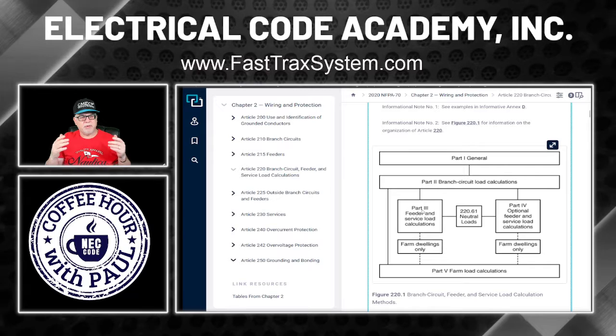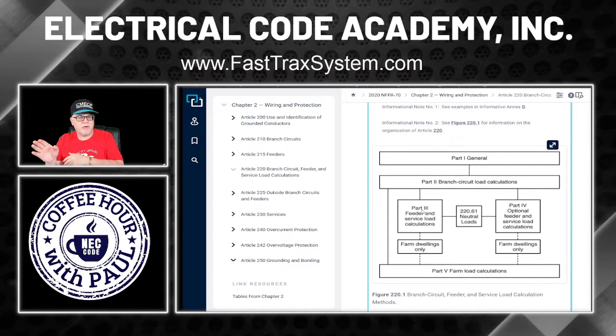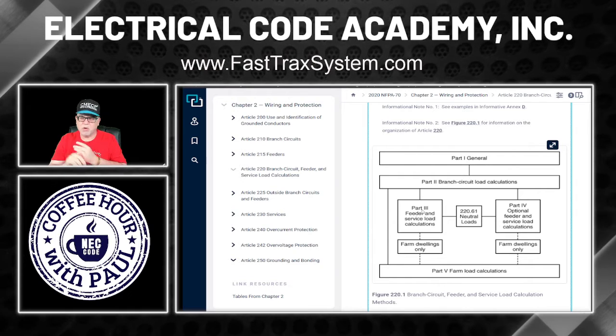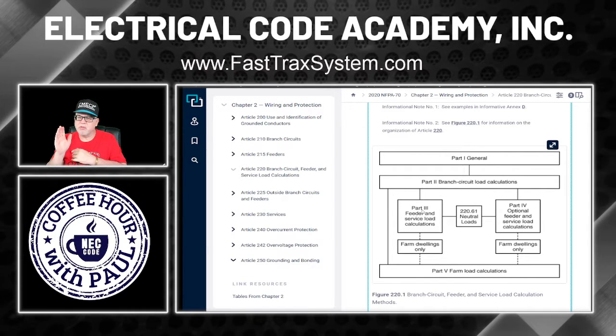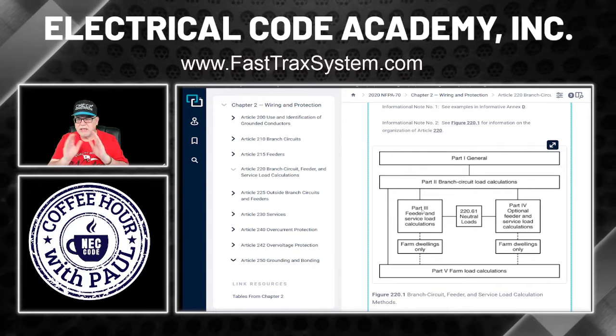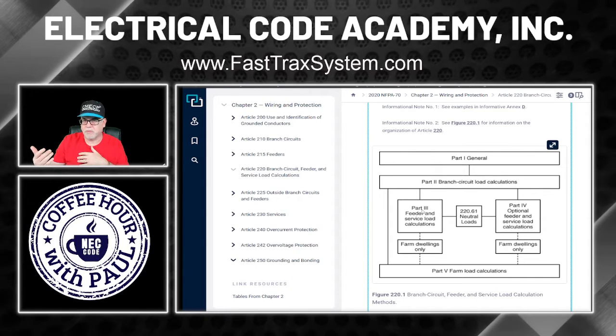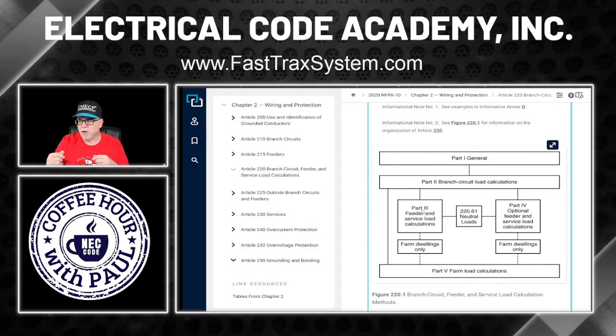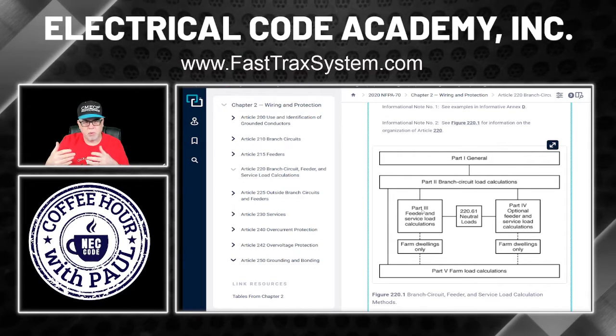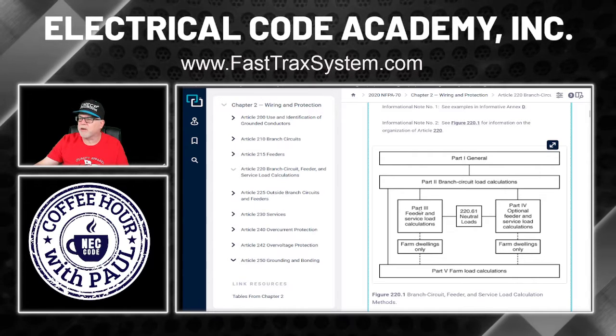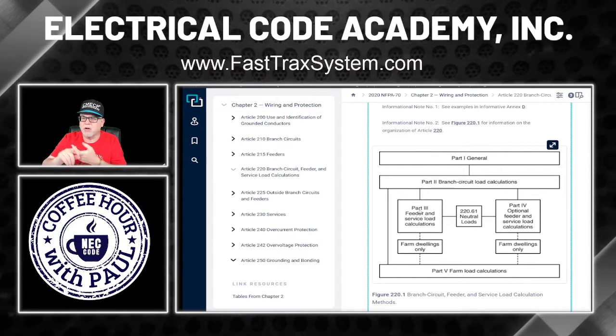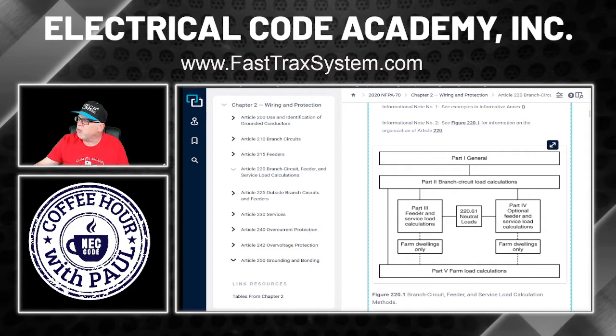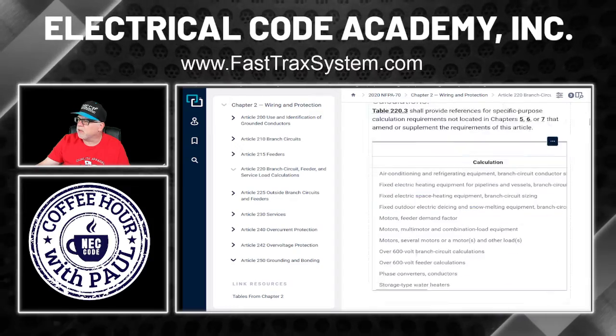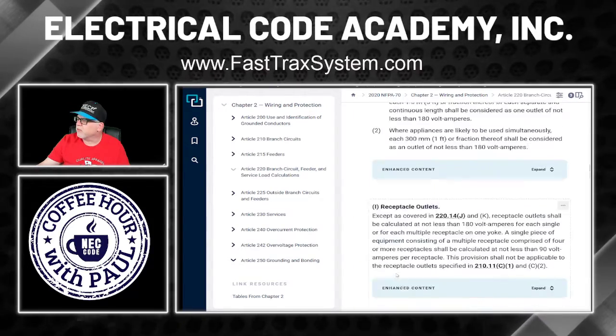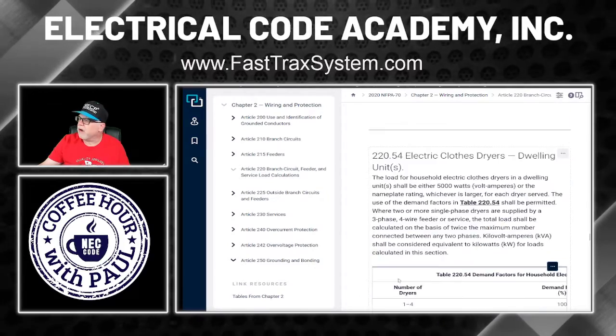So a key thing to remember here is that unless they state optional, you're always going to use the standard. Of course, in this case, the VA values are not going to matter, but you should always remember that they have to give you the information, and it's always considered the standard unless they state otherwise to use an optional method. So standard, being the general way to do it, is in part 3, and then the optional is in part 4. Okay, so let's go on. We're looking specifically for small appliance and laundry, so we can go to part 3 of this, because we're doing a load calc.